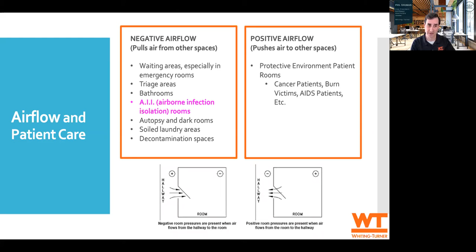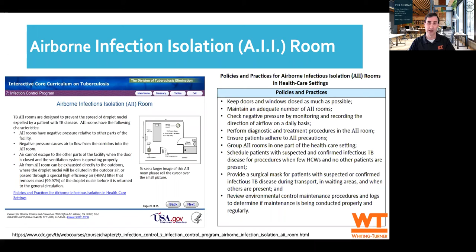Design, construction, and use of AII rooms have many requirements. Some are handled by simple standard operating procedures, such as wearing a mask when you enter a room. But some have a larger impact on the use of energy in a hospital, specifically negative air rooms, where the contaminated air must be vented fully outside, effectively making air changes a once-through process without the benefit of recovering the heating and cooling we've already put money into once. Slide.